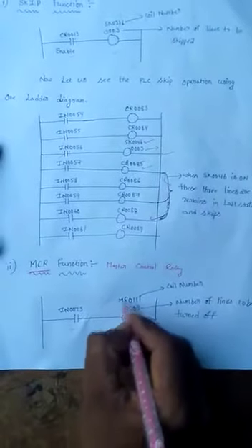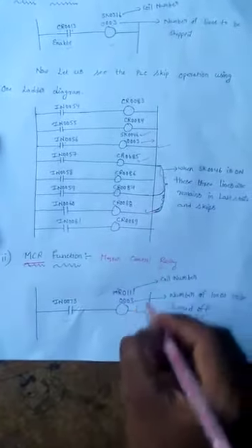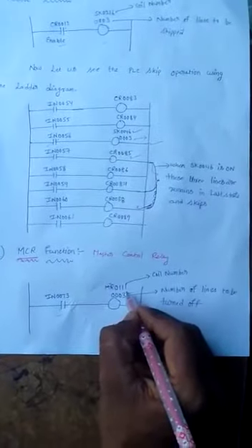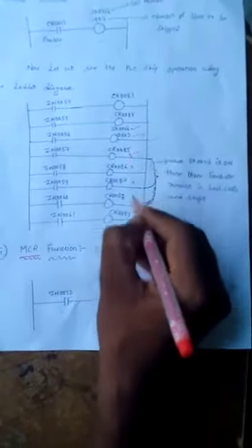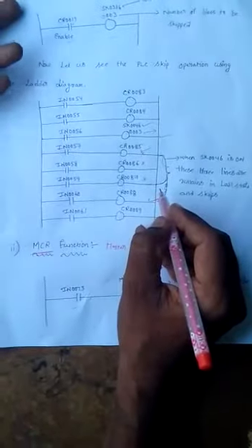But when we activate the MCR function, the master control relay function, the represented lines, here also 3 lines, will be turned off. That means all the outputs are frozen off. That is the difference between the skip function and the MCR function.